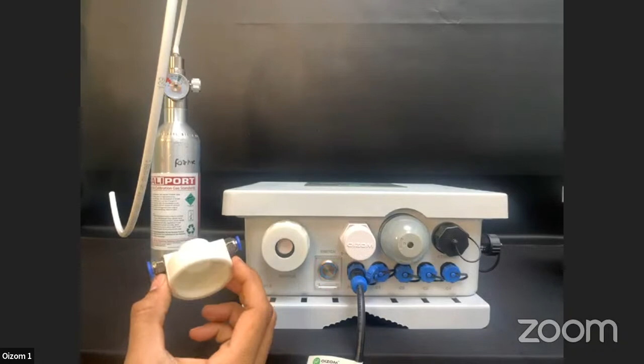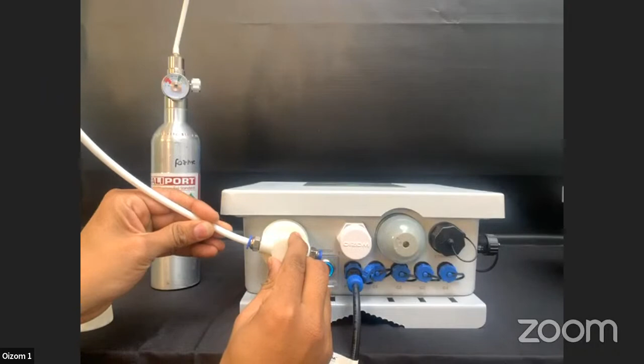Yeah, so it's very easy to replace the current OGS cap and then put this on it. As quickly as it's been shown on the video here, this is how you can do it in the field. Once it is done, and once you connect the device to any smart device, you can then perform site calibration in the field. There are the connectors, the blue ones that you see, and the tube from the gas cylinder is connected to it, and you just need to turn on the regulator, which is somewhere around 0.5 liters per minute. Once you do that, the zero air is passed and then you can perform the calibration.